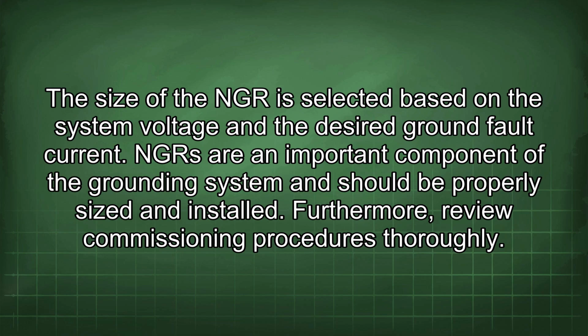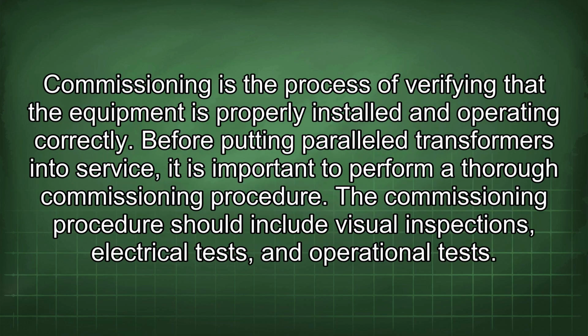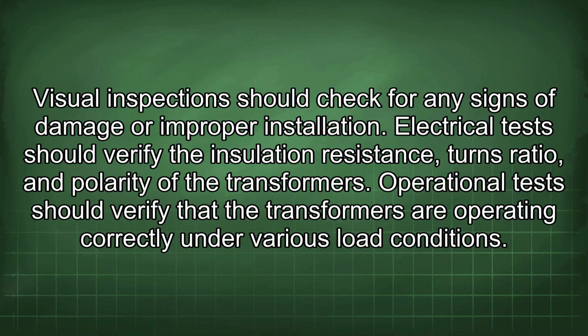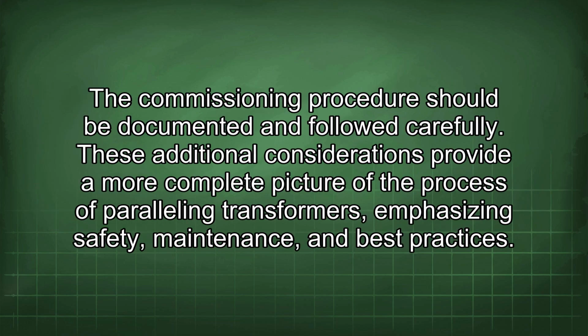Furthermore, review commissioning procedures thoroughly. Commissioning is the process of verifying that the equipment is properly installed and operating correctly. Before putting parallel transformers into service, it is important to perform a thorough commissioning procedure. The commissioning procedure should include visual inspections, electrical tests, and operational tests. Visual inspection should check for any signs of damage or improper installation. Electrical tests should verify the insulation resistance, turns ratio, and polarity of the transformers. Operational tests should verify that the transformers are operating correctly under various load conditions. The commissioning procedure should be documented and followed carefully. These additional considerations provide a more complete picture of the process of paralleling transformers, emphasizing safety, maintenance, and best practices.